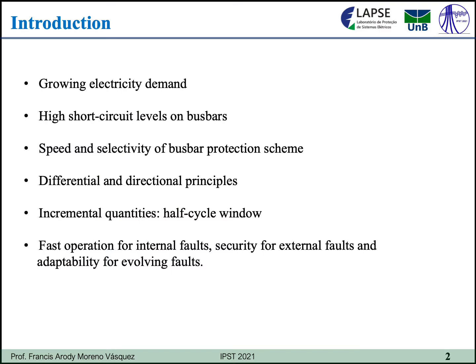So, I must begin by saying that the growing electricity demand led to the construction of more transmission lines, inclusion of more power transformers, and connection of more feeders in busbars. And that means that short circuit levels are higher. In this scenario, the speed and selectivity of busbar protection schemes are very critical in order to guarantee the stability of the power system.